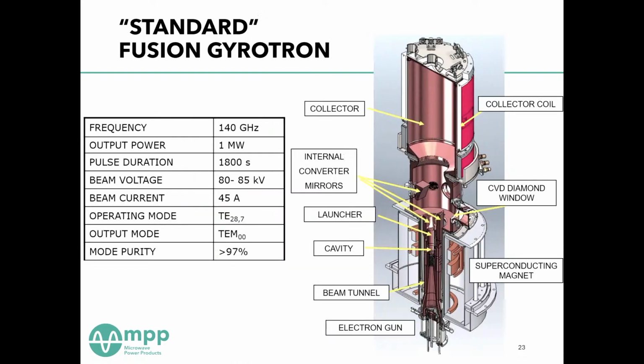So moving from cartoon to solid model, on the right is what a gyrotron sort of looks like. Down at the bottom is our electron gun. We have an area between the gun and our interaction where the electron beam is being compressed by the magnetic field. The gyrotron sits in its superconducting magnet, and the cavity, the interaction space, is right at the high field region, right in the middle of the magnet. We've got some mode converter, and then this is a little bit more realistic. It indicates that the collector is the single biggest part of the gyrotron, because we're about 50-ish% efficient. So to make a megawatt gyrotron, you've got a whole other megawatt of electron beam that has to be safely dissipated somewhere. And that's also easier said than done.